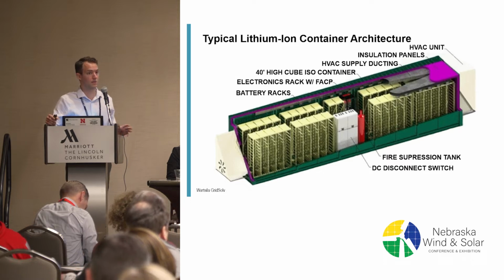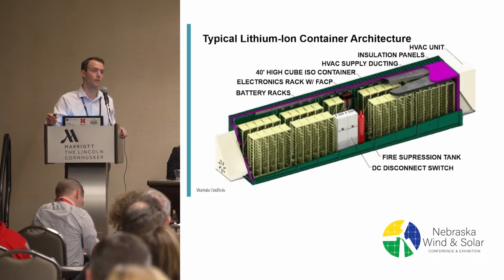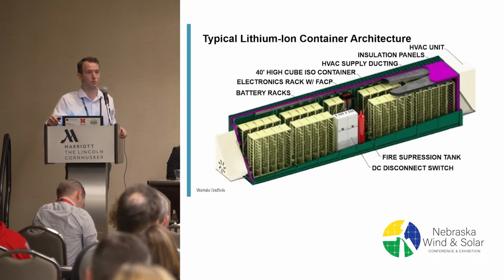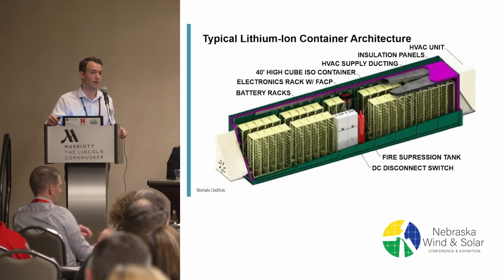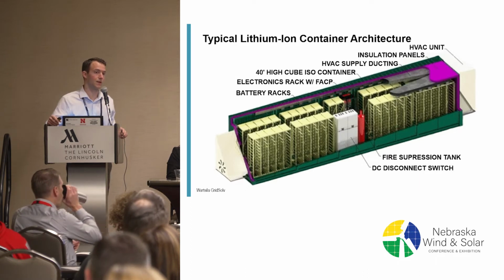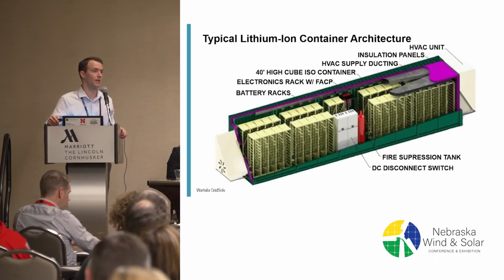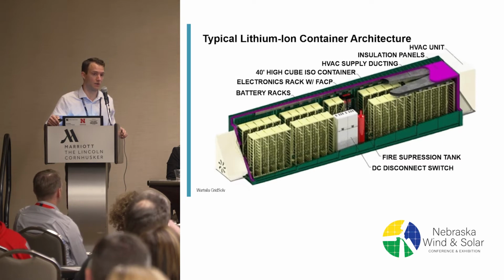That system in most cases is going to require an auxiliary power supply, an external power supply. There are some instances where that's pulled off of the battery DC bus internally, but by and large, another thing to think about with site design is that auxiliary power supply, where you're getting it from, how you're metering it, and how that's being accounted for in your round trip efficiency. All kinds of things about aux power supply that are fun to explore.